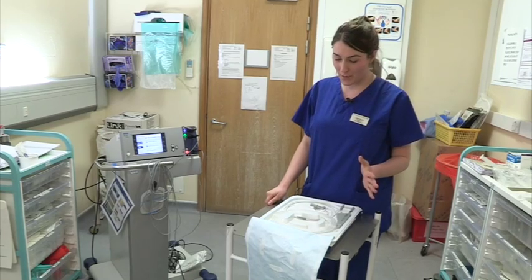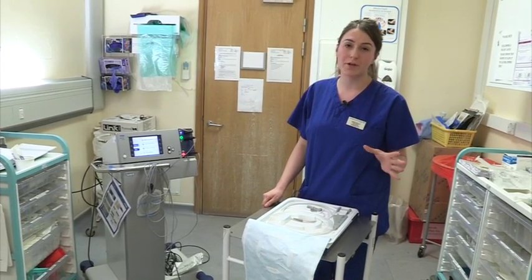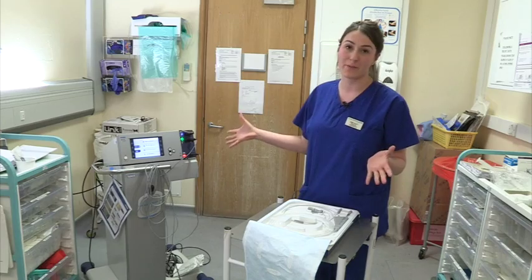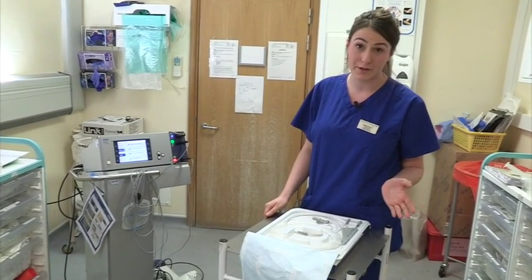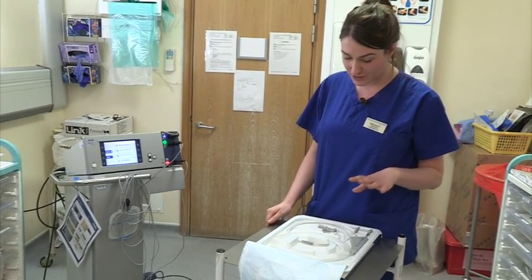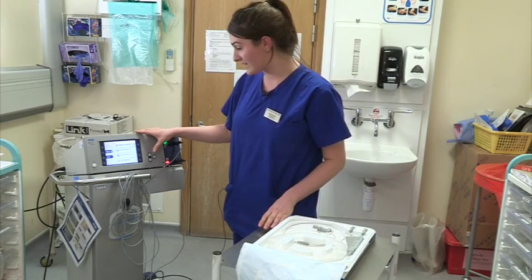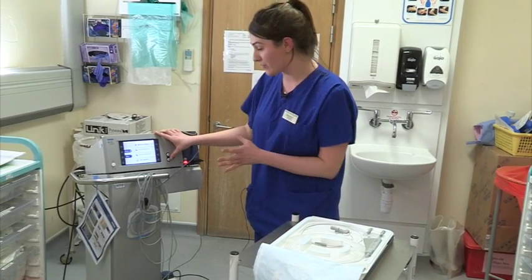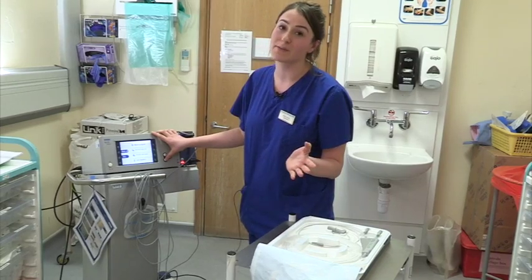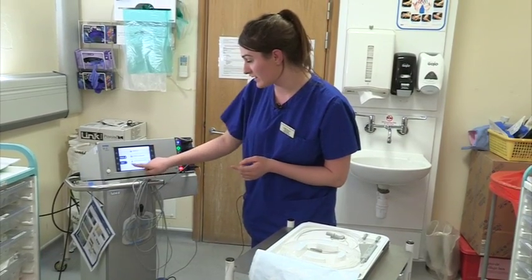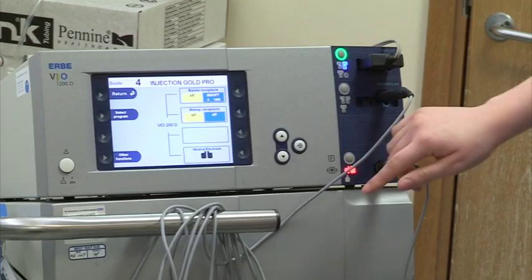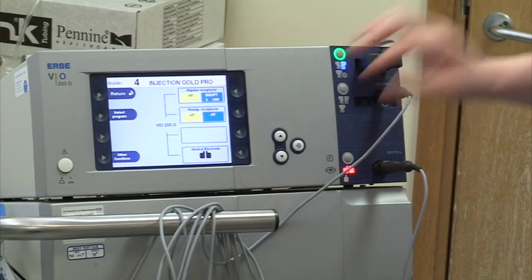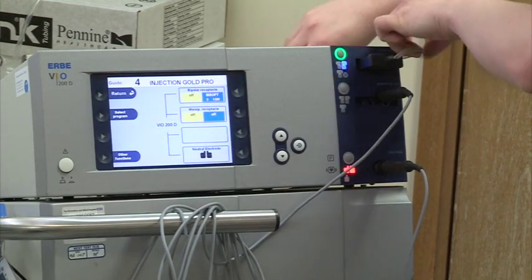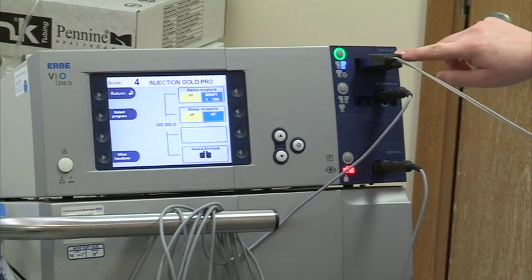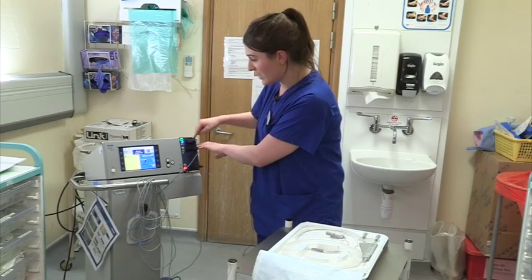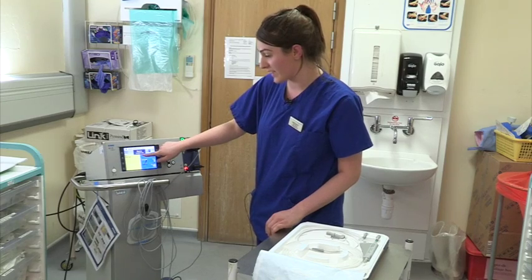Okay, so setting up the gold probe, just make sure that all the equipment you use is compatible with your Erbe diathermy machine that you have and the endoscopes that you use. Then make sure that you have your Erbe set up on the correct setting. We're quite lucky and ours is programmed correctly, so just talk to any reps for the equipment that you do use. So we are going to set it up onto injection gold probe, and I'm going to select the program. And then you need to change the setting of the machine to bipolar, which on our machine is just this button here. And now we've changed to bipolar, which it tells you on the screen.